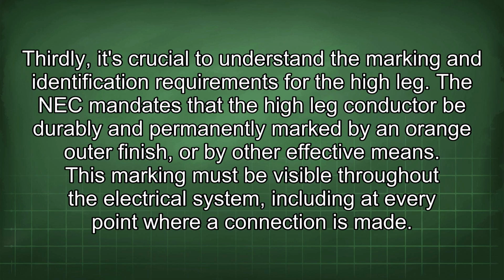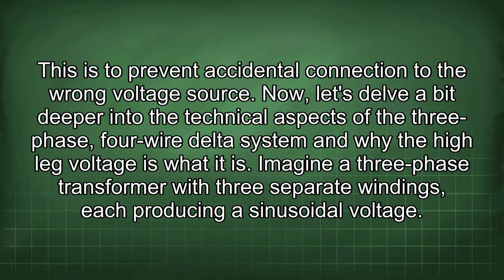Thirdly, it's crucial to understand the marking and identification requirements for the high leg. The NEC mandates that the high leg conductor be durably and permanently marked by an orange outer finish, or by other effective means. This marking must be visible throughout the electrical system, including at every point where a connection is made. This is to prevent accidental connection to the wrong voltage source.